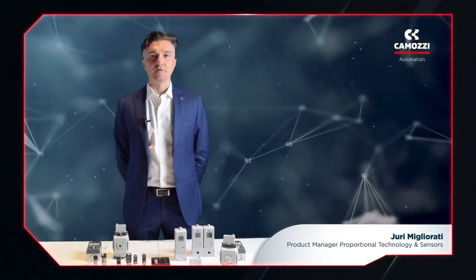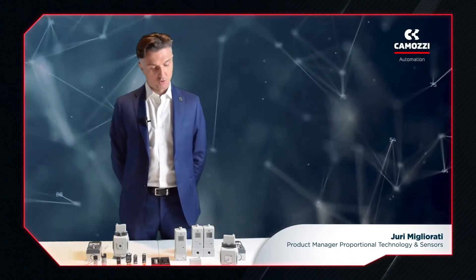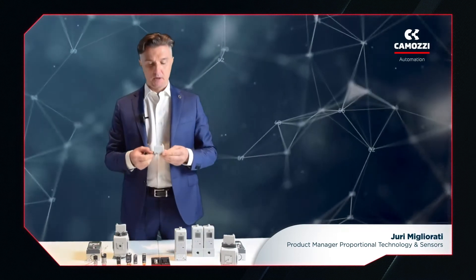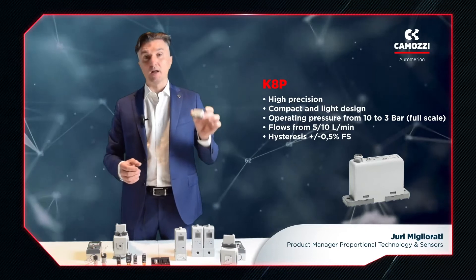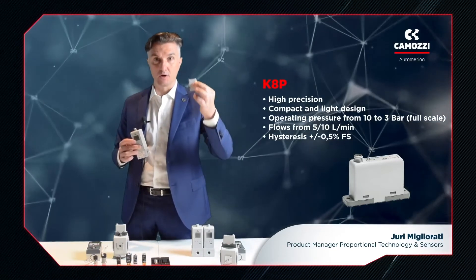Now let's talk about the other family: proportional regulators. Camozzi's range is divided into five series. The smallest series is the K8P, a matchbox-sized proportional regulator with a flow rate of 5 to 10 NL per minute and with working pressures between 3 and 10 bar. This performance compares favorably with larger regulators and even has very similar hysteresis, repeatability and linearity. It's also often used as a signal amplifier.